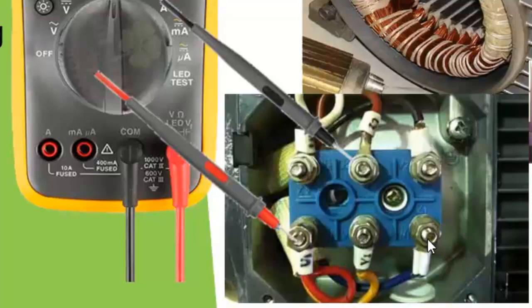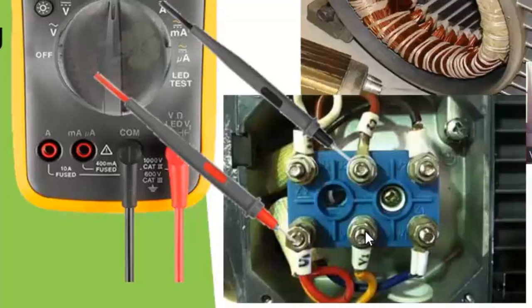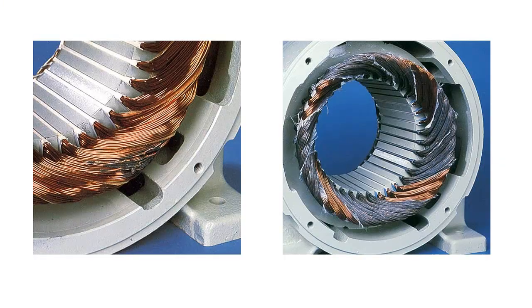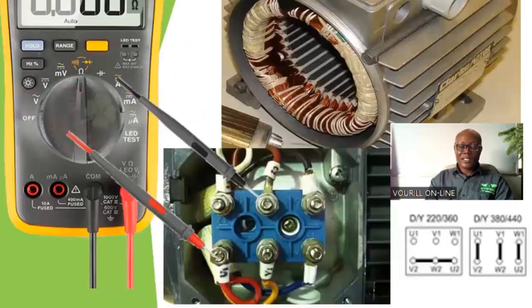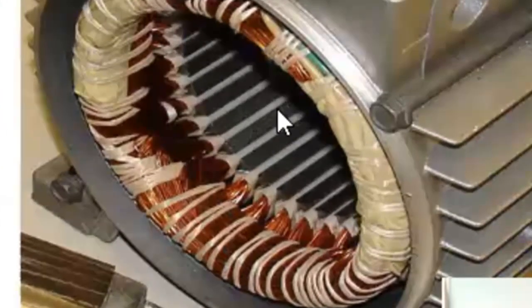So once there is something like that, it is now left for you to know that definitely the electric motor needs repairs. You have to fix those windings. Then burnt winding. Burnt winding could be evident when you open it up like this and then inspect the motor. You could see the burnt around the winding. But there are some that will happen in the middle of the slot that may not be too visible.